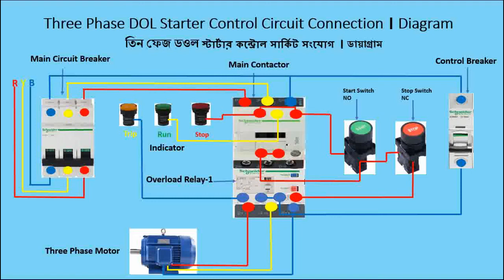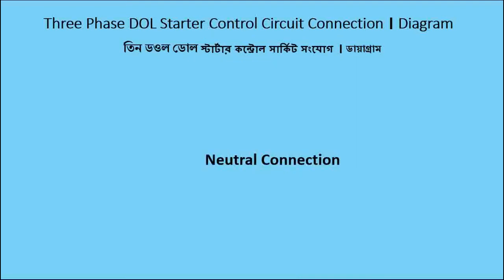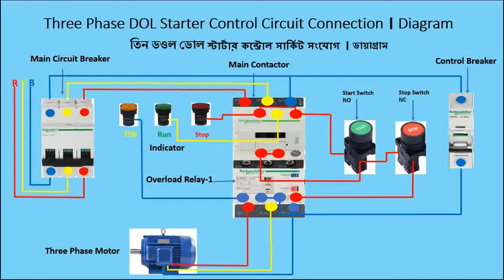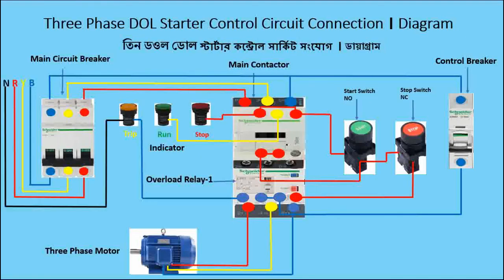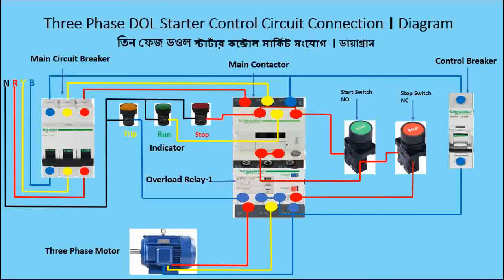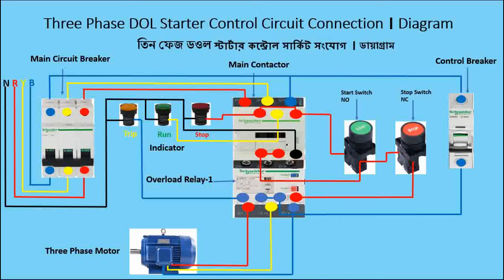The control wiring is complete. Now I will show the neutral wire connection. Neutral is only for control — the neutral wire first goes to the first indicator, then the second indicator, then the third indicator, then to the main contactor. This is the total wiring for the three-phase DOL starter control circuit connection.